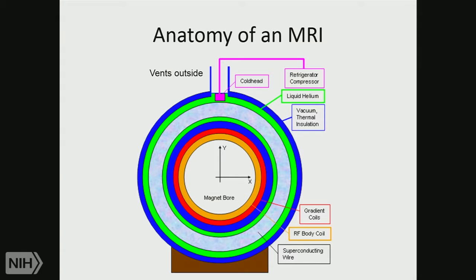Right behind that are the gradient coils. Remember I said to get spatial recognition, you need to apply these magnetic gradients, and so that's what comes next. Then there's an insulator, and then there's this space, which is super cooled to near absolute zero, and it has titanium wire in it, and through that the magnet is charged up with a huge amount of energy. When a magnet is commissioned, they come in with a generator and essentially apply a huge amount of energy to these superconducting wires. They fire up, and they're an electromagnet. So they generate a huge magnetic field that's steady, like a rock.